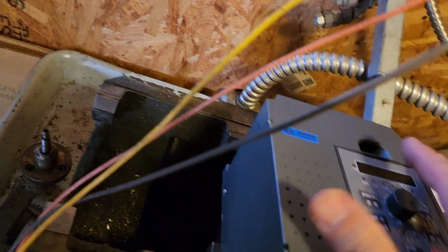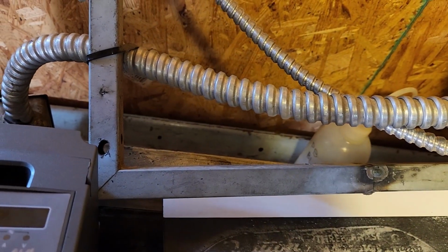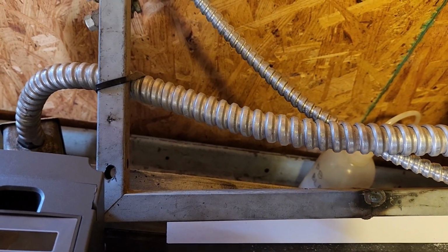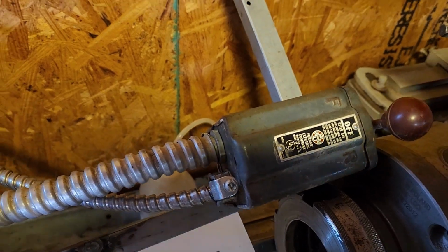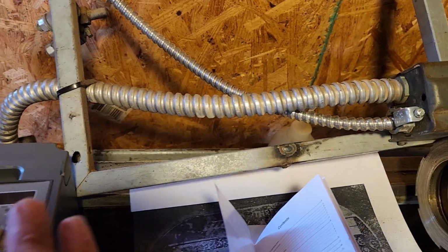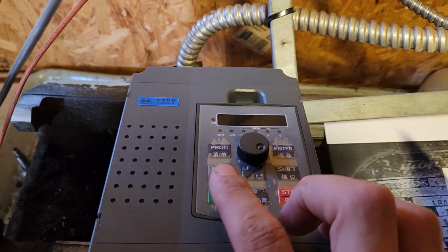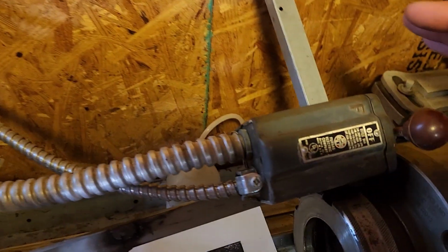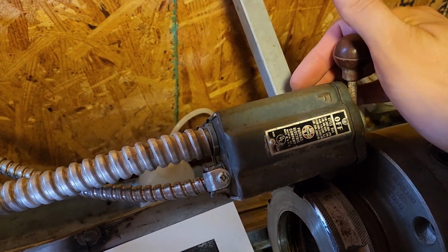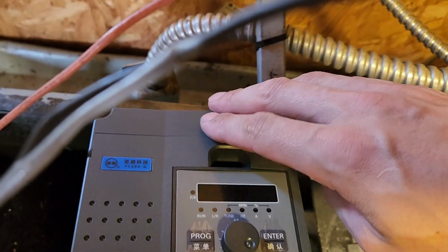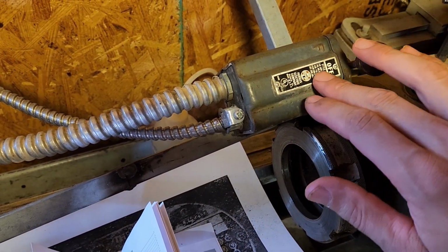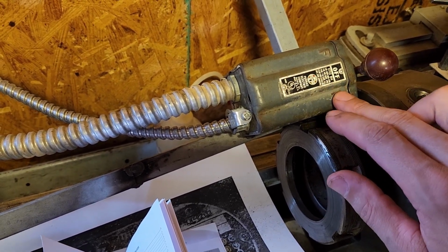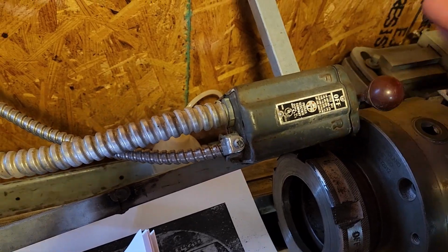What I can do is look through the manual and find an input for just run. You start this in the off position, the VFD turns on, and the VFD will not do anything until you hit run. But you can set it up so that this would be your run signal, and that would start the VFD in forward. And then there should also be an input that will tell it to run reverse, so I can wire up 2 other wires so that I can use this control. Because it's old, it's cool looking, so I'll use that to do forward and reverse.